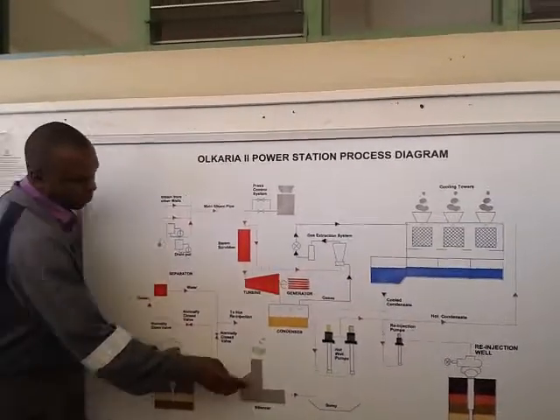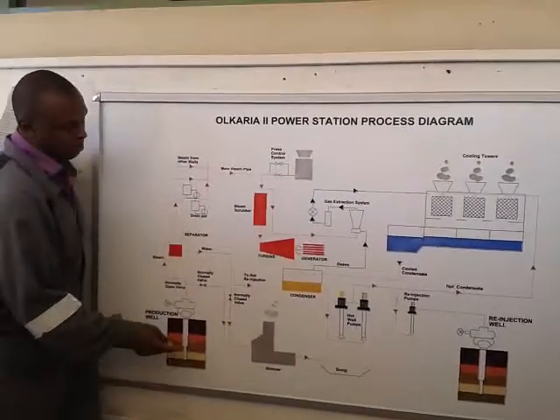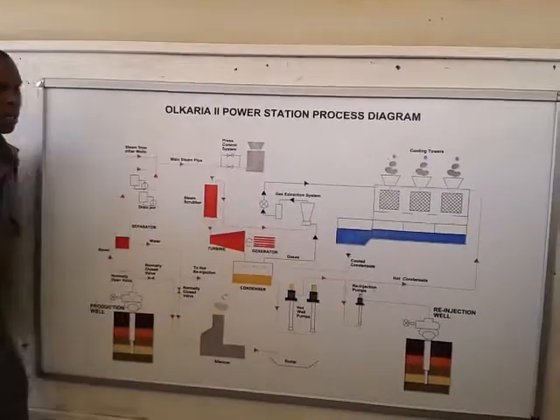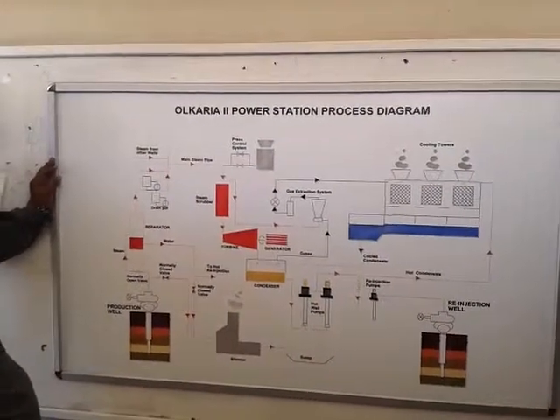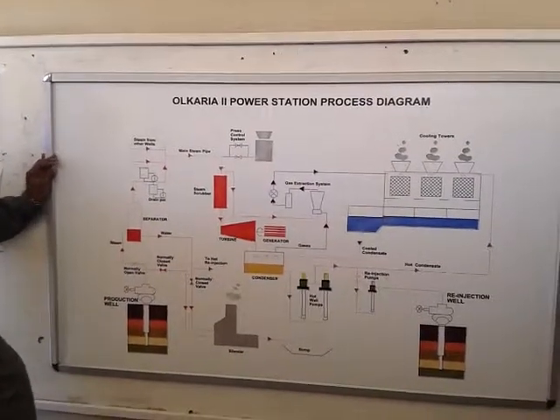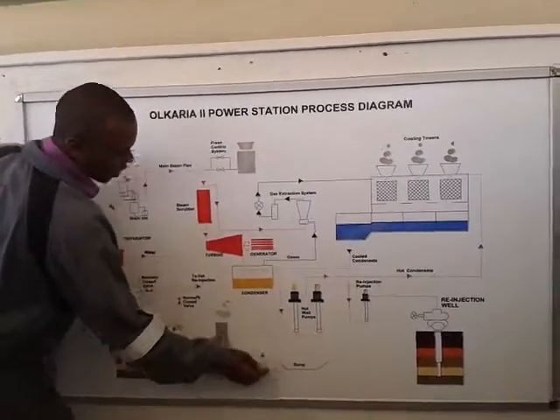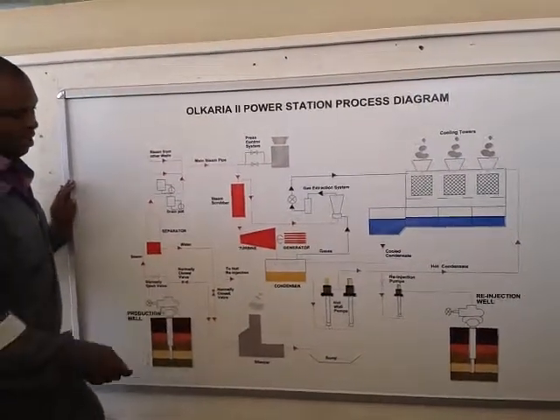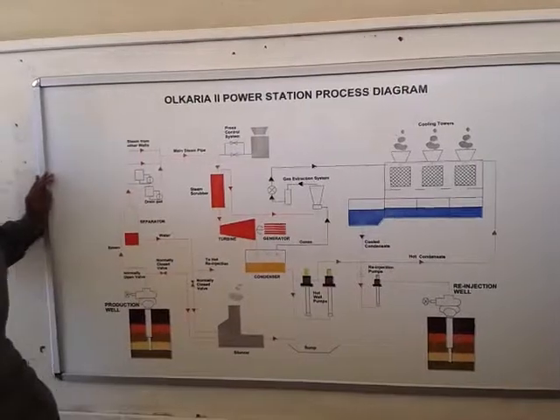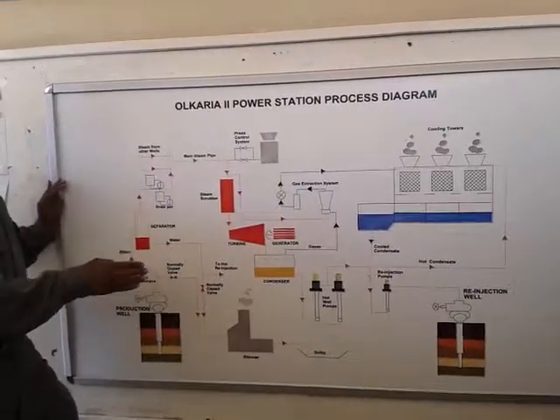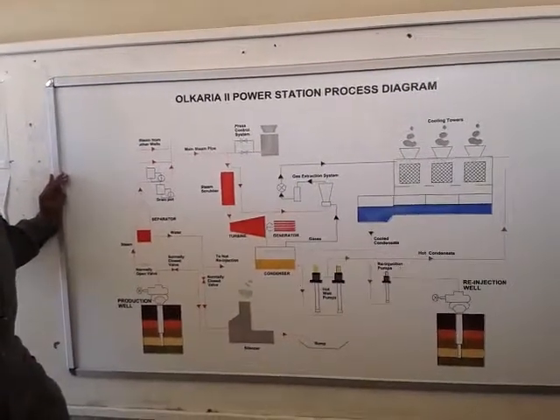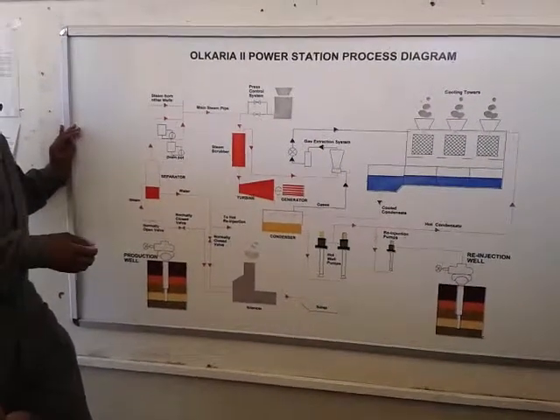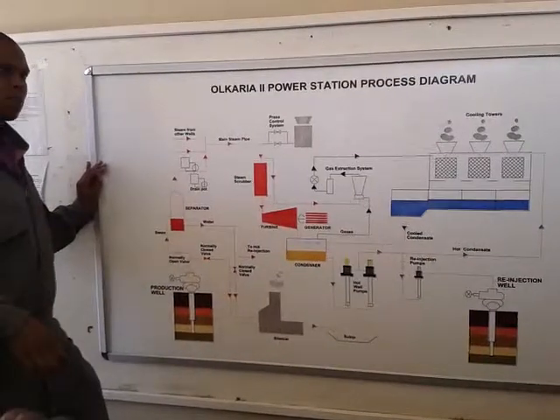Then it will be channeled to a sump via a silencer. A sump is a drainage point — the separated brine water collects there. When that sump is full, they use a mobile pump to suck that brine water and pump it into an injection well. Geothermal is a reliable source. After separating that brine water, they return it back to the ground.